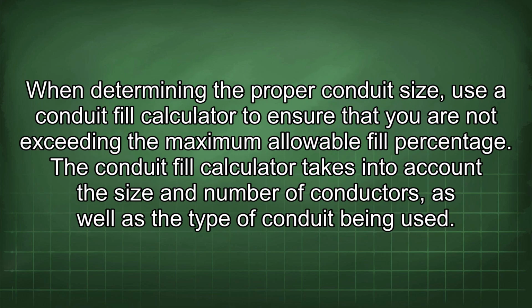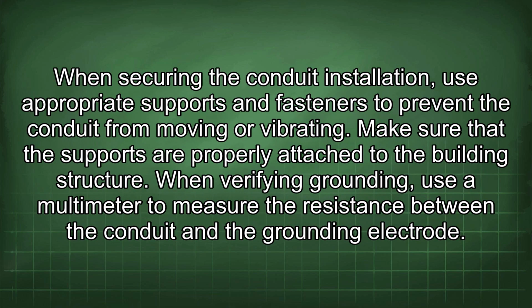When determining the proper conduit size, use a conduit fill calculator to ensure that you are not exceeding the maximum allowable fill percentage. The conduit fill calculator takes into account the size and number of conductors, as well as the type of conduit being used. When securing the conduit installation, use appropriate supports and fasteners to prevent the conduit from moving or vibrating. Make sure that the supports are properly attached to the building structure.